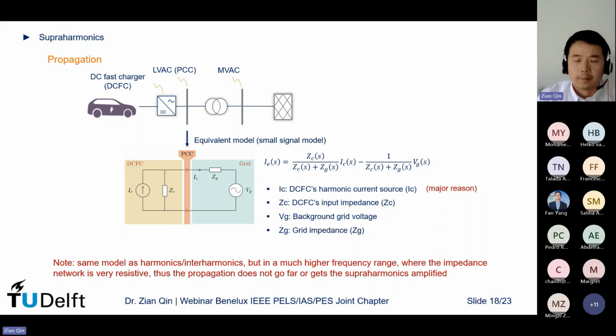Therefore, this impedance network will very likely be overdamped, which means if you still see a supraharmonic issue at this PCC point, it is not because the harmonic emission is amplified or the background noise is amplified here, because it is a very over-damped impedance network.